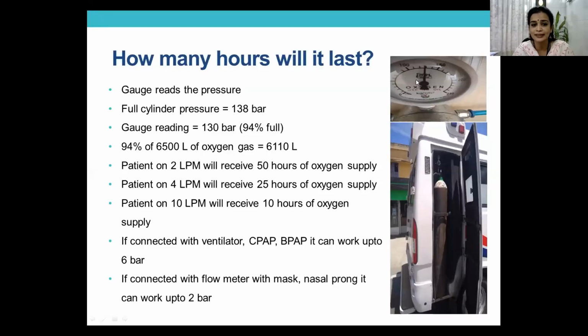This is not liquid, this is gas. So if your patient is on 2 liters per minute, you can take this patient from probably Kanyakumari to Kashmir, 50 hours of oxygen supply it will have. If the patient is on 4 liters per minute, 25 hours. So how do you calculate this? It has about 6,110 liters. And then you convert 2 liters into 60 minutes into 24 hours, divide, and then you will know exactly how many hours it is going to last you.